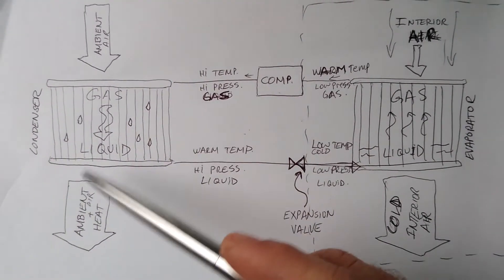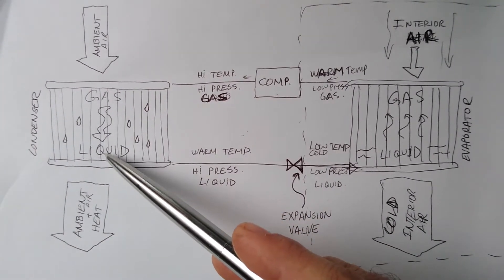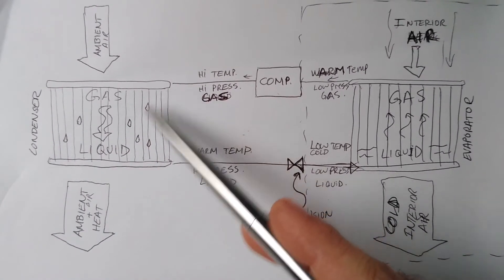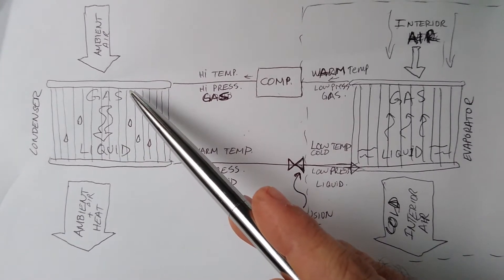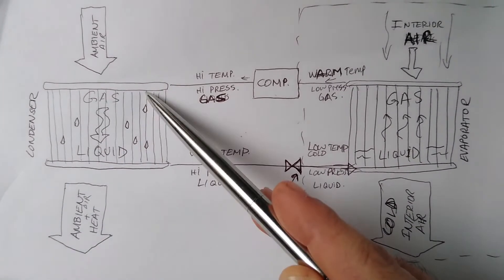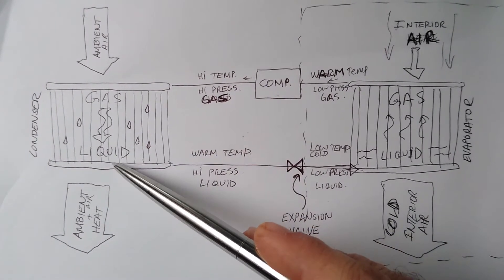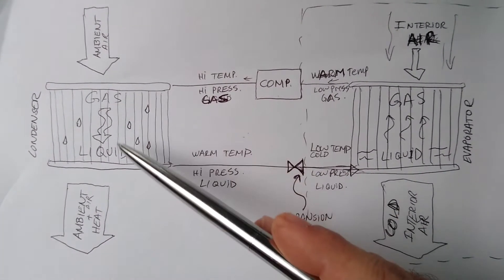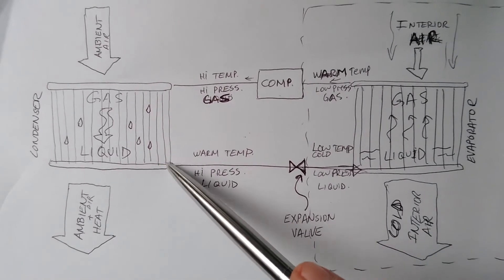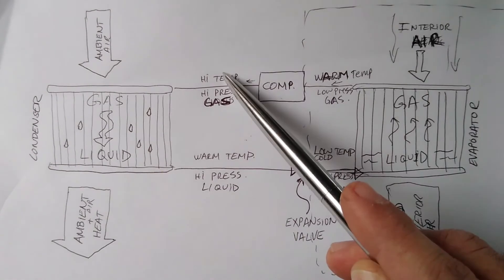When the ambient air draws heat away from the gas, the gas can become cold enough to condense into a liquid. The pressure is still high — only slightly lower than before — but the refrigerant is now in liquid form. In the condenser, the gas goes from gas to liquid, and that phase change happens because we're taking heat away from it.